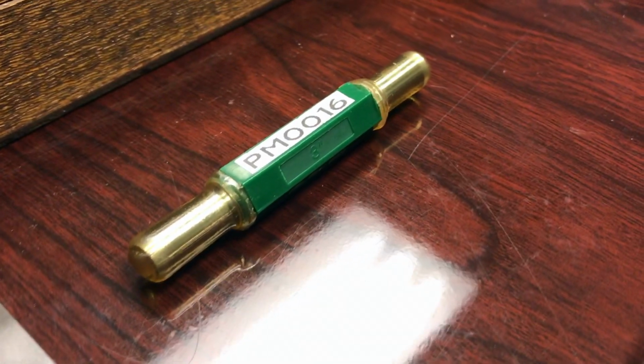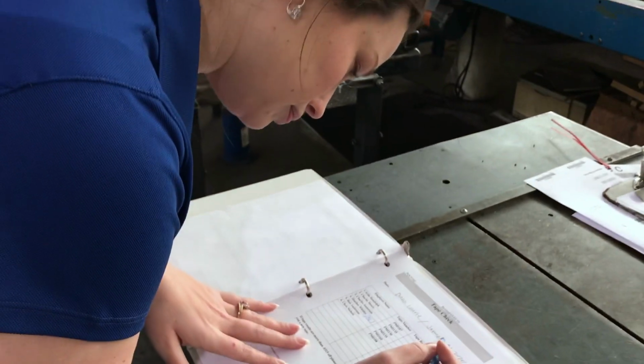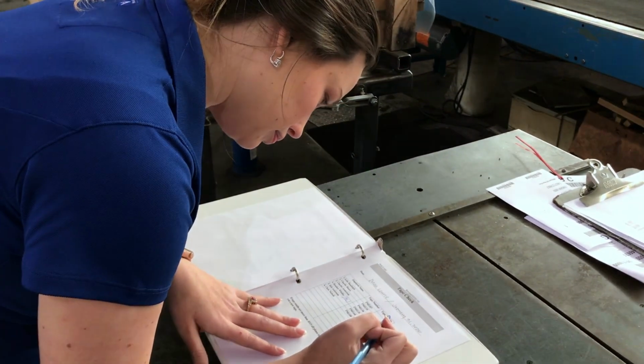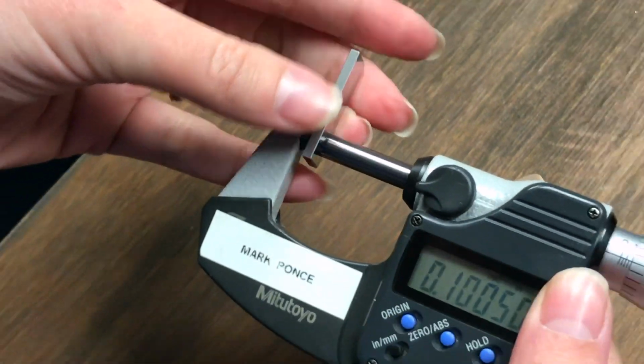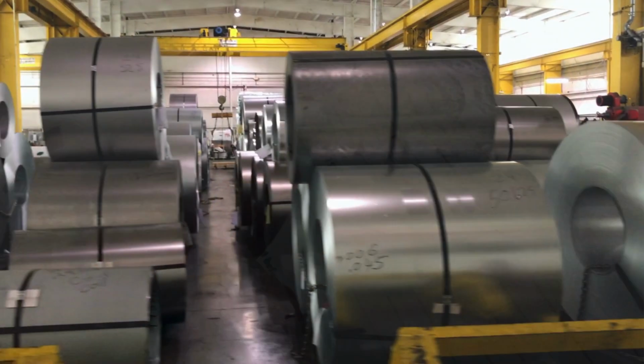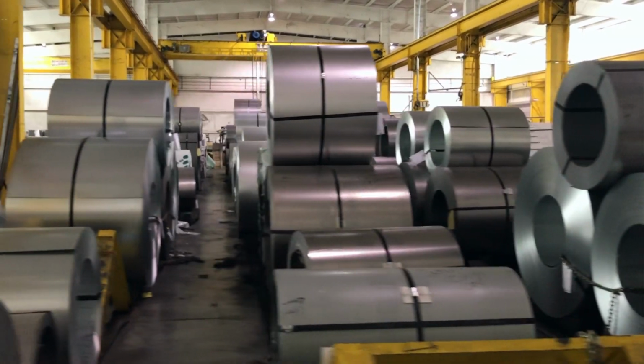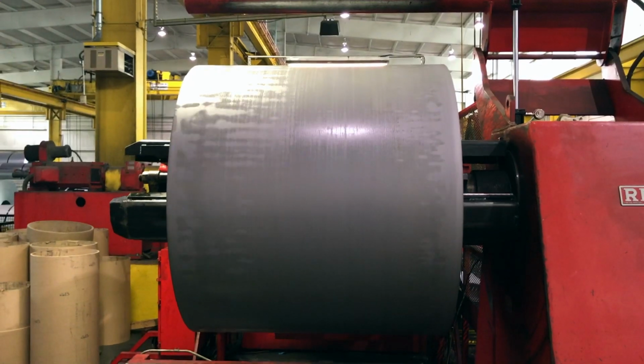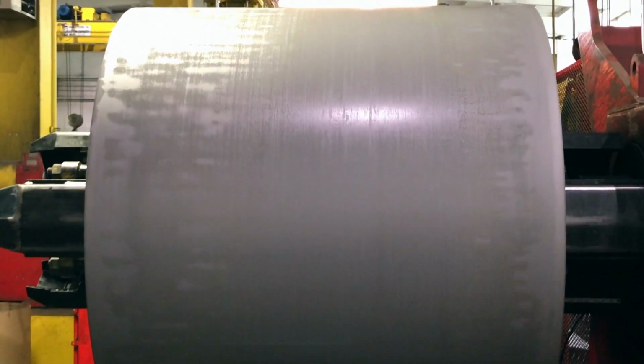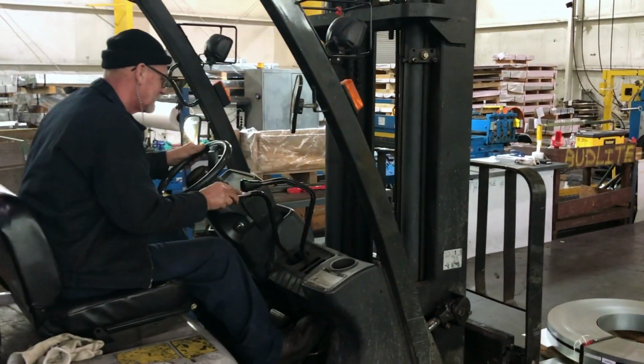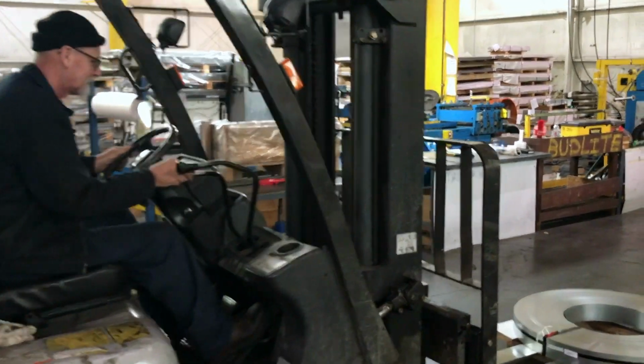So essentially what that means is that we are taking our micrometers, we're measuring our linear table, we're using standards on both of those instruments to ensure the precision and accuracy of all of the steel that we measure throughout the plant. This is just to ensure that every product that you get is absolutely accurate. We use these standards for calibration reference, and we have caliper checks and tape measure checks as well.